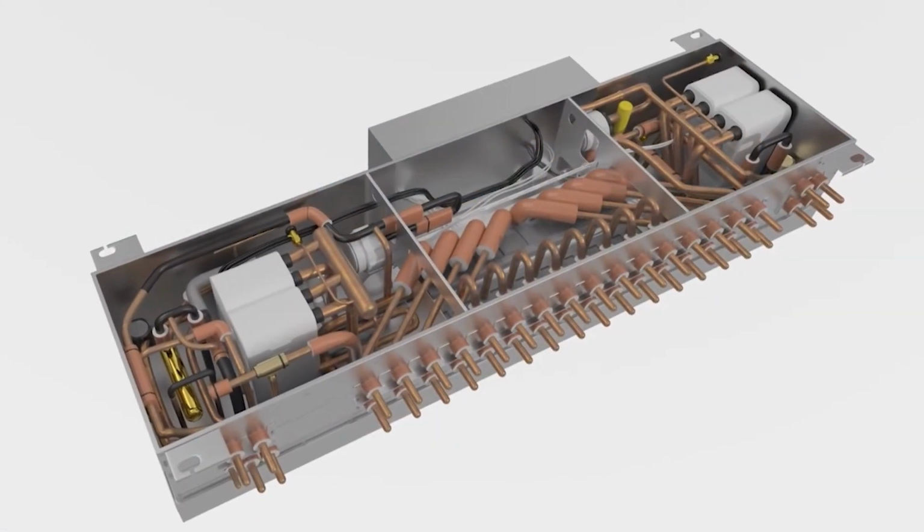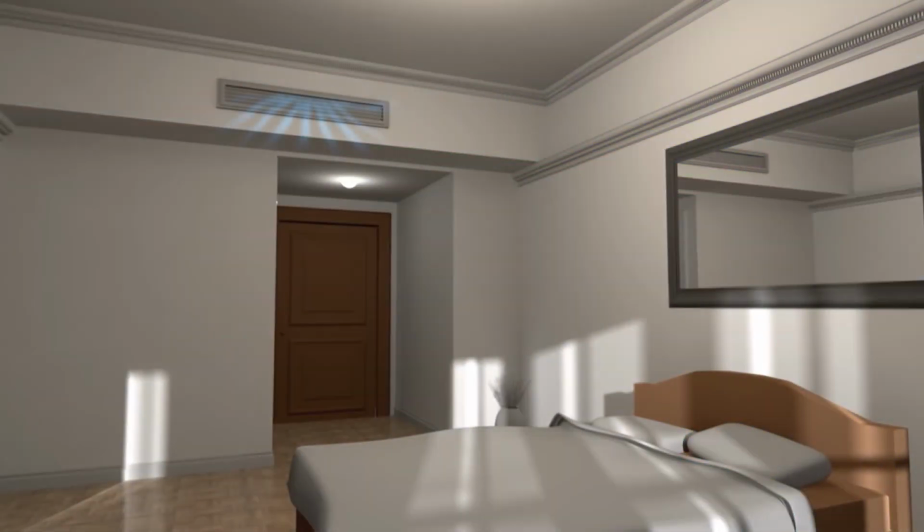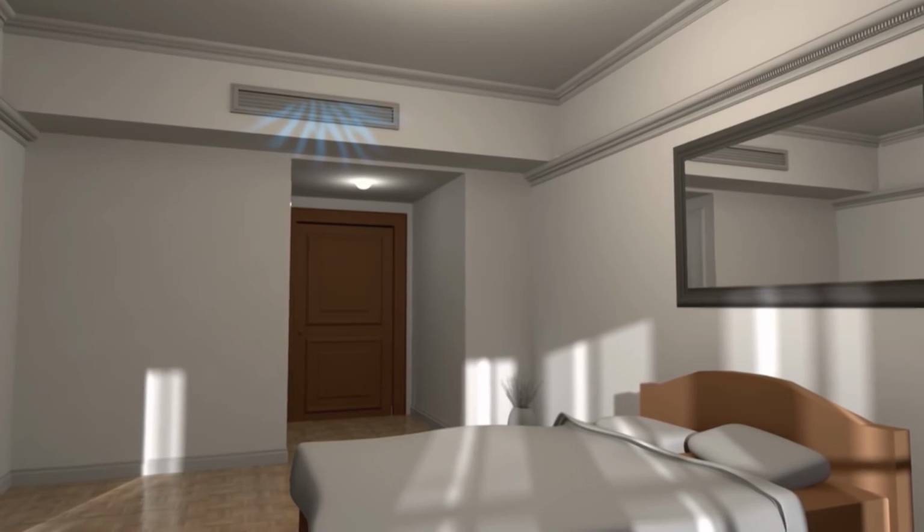The HVRF concept gives us the best of both worlds, a low GWP refrigerant and water for circulating the heat and air inside the building. Hybrid VRF is a unique two-pipe heat recovery system that replaces refrigerant with water from the indoor branch controller to the occupied space within the building, which addresses ASHRAE 15 and 34 concerns. Hybrid VRF is able to modulate refrigerant flow, fan speed, and water flow to match the loads, and it provides energy-efficient, zoned comfort.